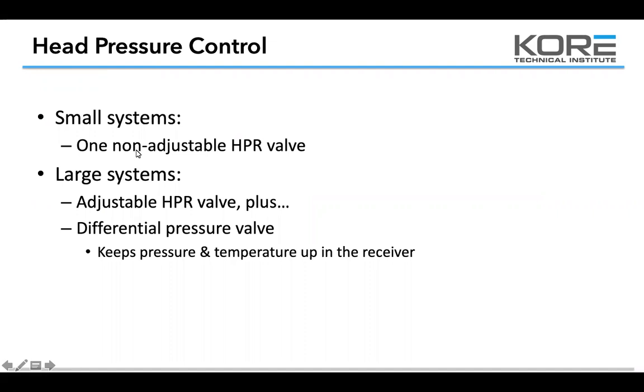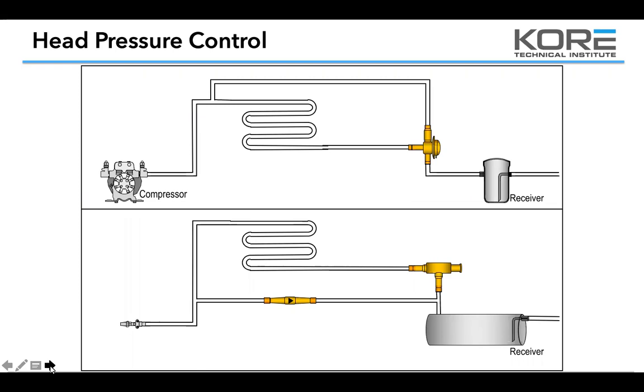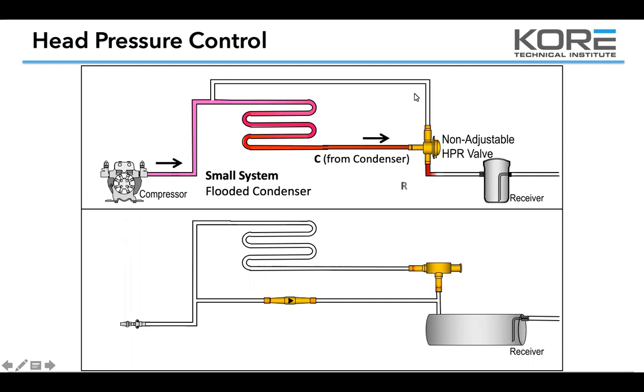Let's talk about head pressure control. On small systems you're going to run a non-adjustable head pressure regulating valve — a headmaster, as we call it in the field. Large systems use an adjustable head pressure regulating valve plus a differential pressure valve. The headmaster has a charge in its head — an inert gas like nitrogen — that always opposes the system pressure. As long as the condenser pressure overcomes that diaphragm, refrigerant keeps feeding through. As the pressure drops through the condenser, it pushes back on that line and starts filling the condenser with liquid, reducing the condensing surface within the condenser, which raises the pressure.